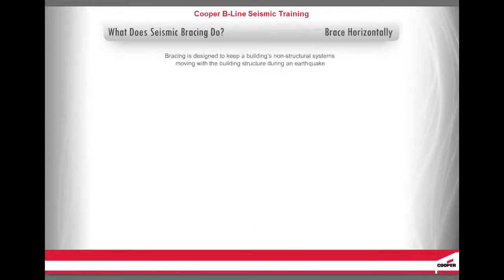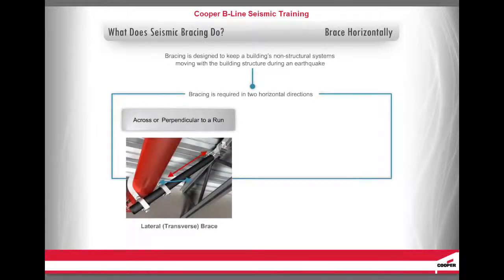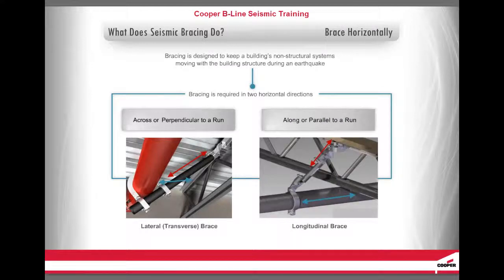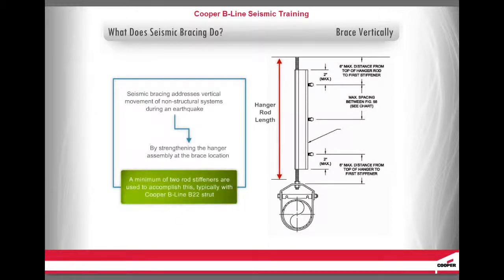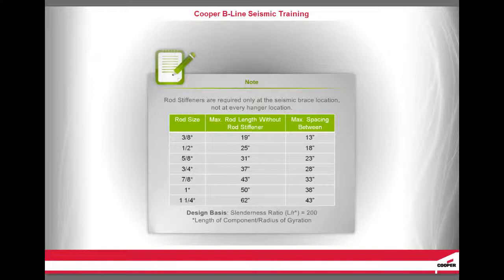Bracing is designed to keep a building's non-structural systems — such as pipe, air duct, or cable tray — moving with the building structure during an earthquake. Bracing is required in two horizontal directions: across or perpendicular to a run, and along or parallel to a run. Seismic bracing also addresses vertical movement by strengthening the hanger assembly at the brace location, using a minimum of two rod stiffeners, typically Cooper B-Line B22 strut. Rod stiffeners are required only at the seismic brace location, not at every hanger location.